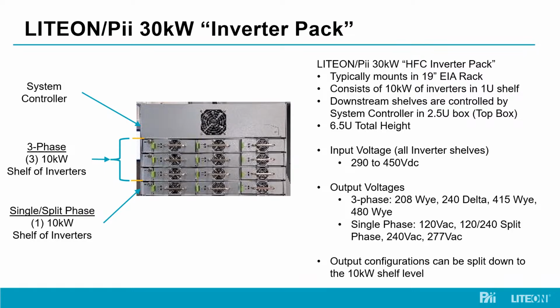So this is a generator application where we're showing three shelves of inverters that each in and of themselves form a phase of three-phase. So three shelves, three phases. I mentioned providing 120, which can create 208 volt Y. We also have 240 delta, 415 Y, 480 Y outputs that can be formed from these shelves. And in the bottom shelf, again, it's just more of a demonstration, which we've also done, is where we can provide single phase output, 120, 240, 277, as well as 120, 240 split phase outputs.